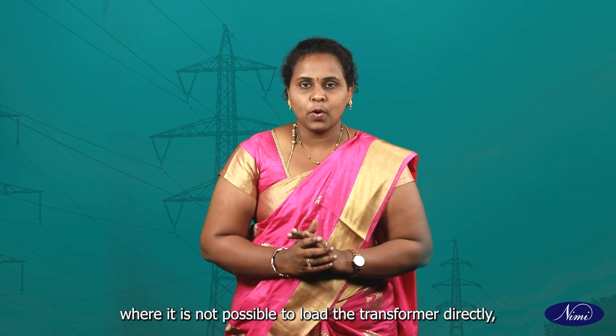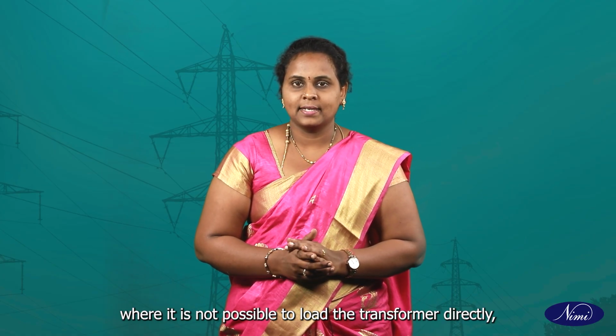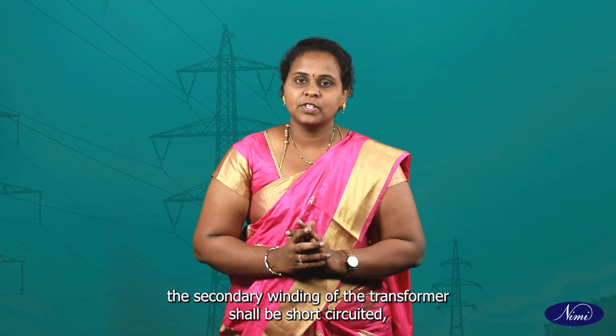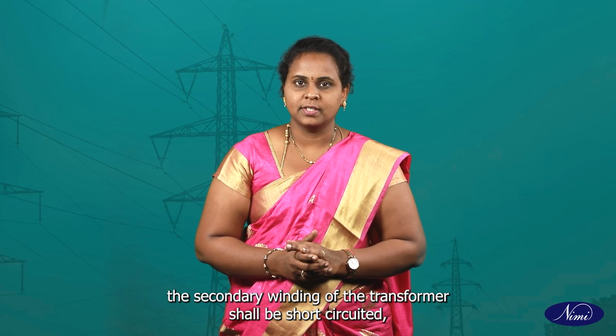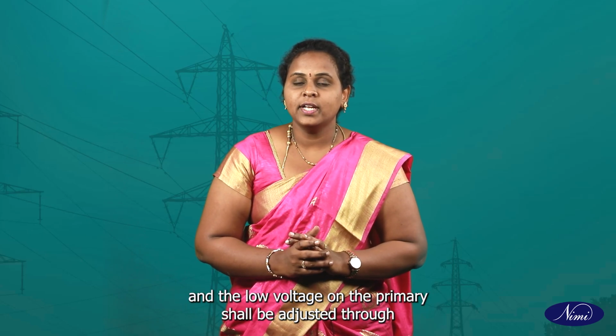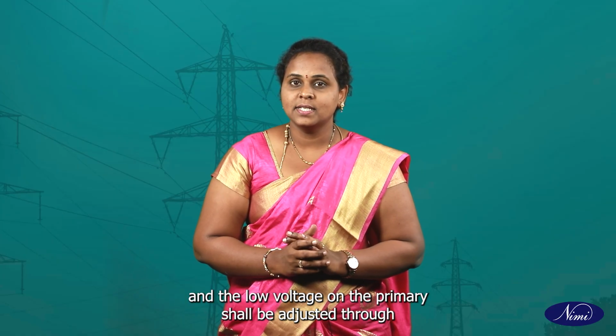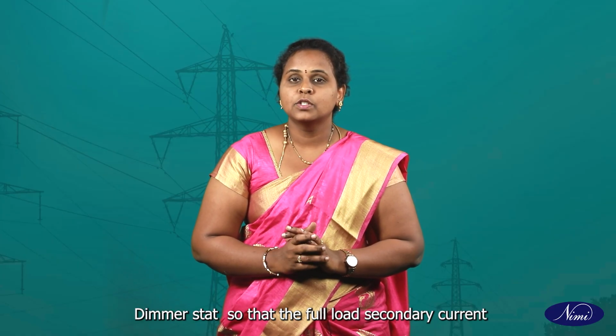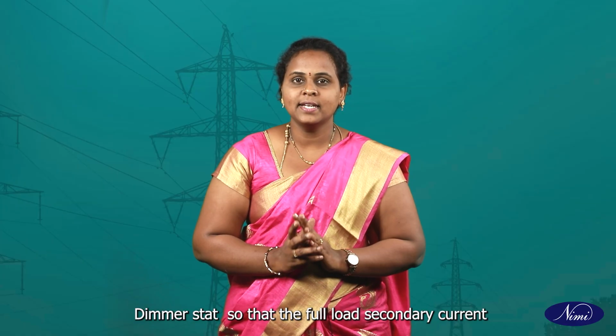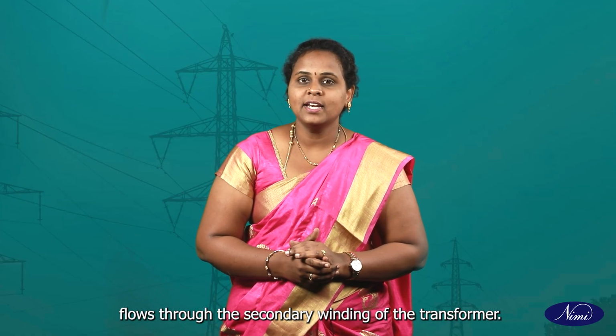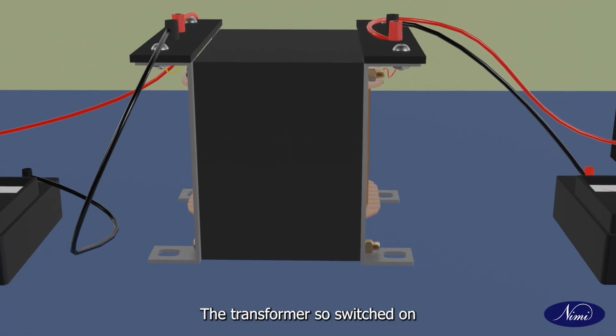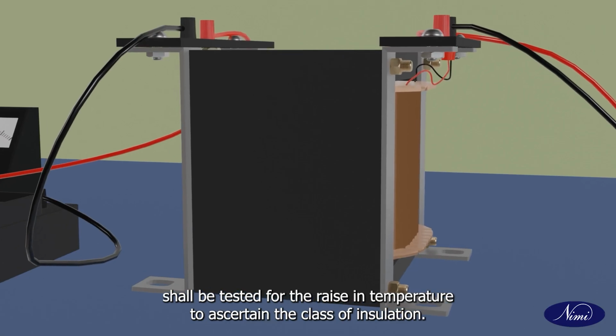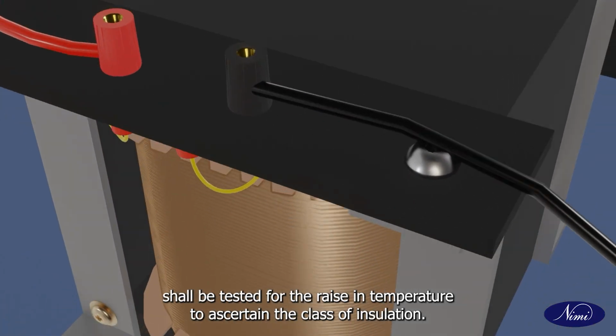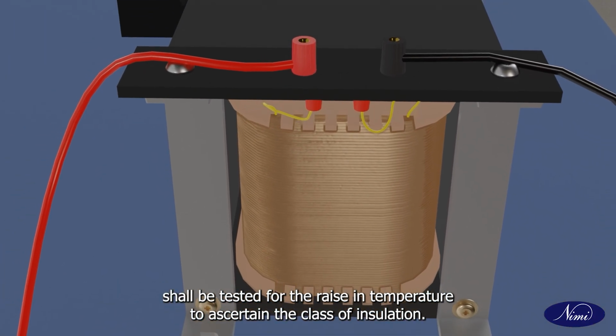Short circuit test. Where it is not possible to load the transformer directly, the secondary winding of the transformer shall be short circuited and the low voltage on the primary shall be adjusted through a dimmerstat so that the full load secondary current flows through the secondary winding of the transformer. The transformer so switched on shall be tested for the rise in temperature to ascertain the class of insulation.